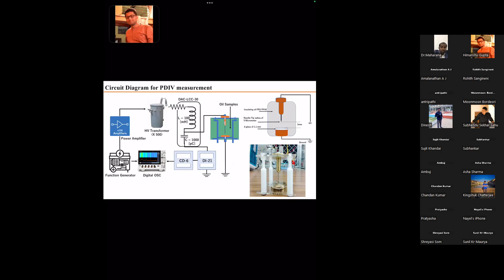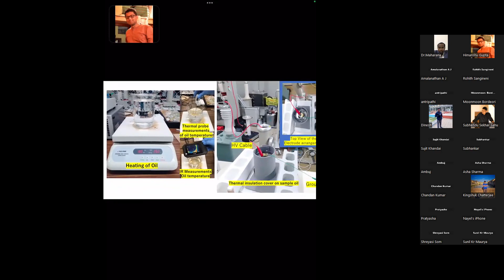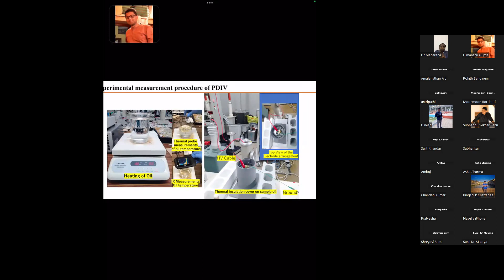As you know, regarding the heating of the oil, in a very closed environment we need to understand the temperature, using a thermal probe and also an IR camera for the surface temperature. Then we put a thermal coating so that the temperature dissipation to the environment is not at a high rate. Though there may be a 2 to 3 degree tolerance, we try to control the temperature in the container, and we measure the partial discharge inception voltage.